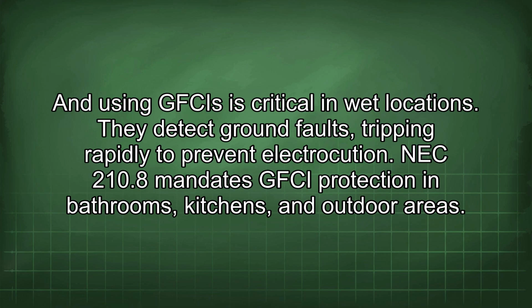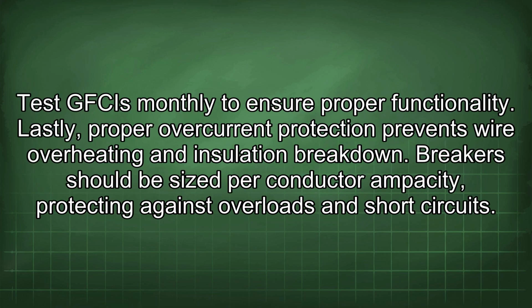And using GFCIs is critical in wet locations. They detect ground faults, tripping rapidly to prevent electrocution. NEC 210.8 mandates GFCI protection in bathrooms, kitchens, and outdoor areas. Test GFCIs monthly to ensure proper functionality.